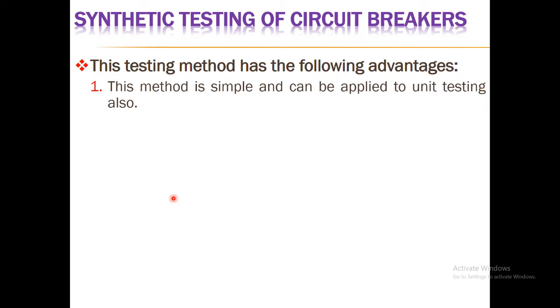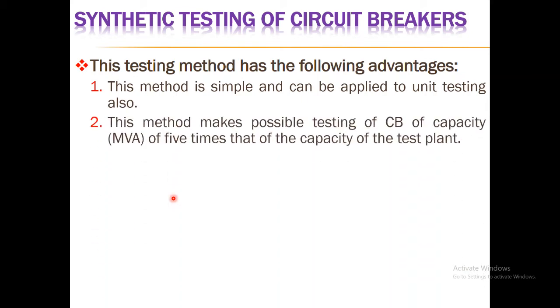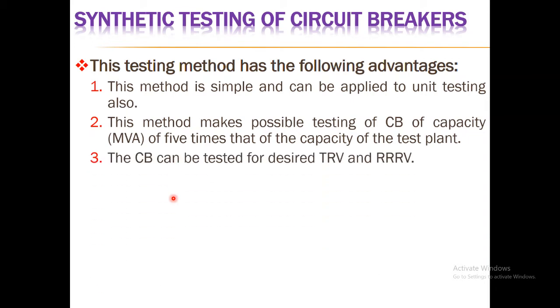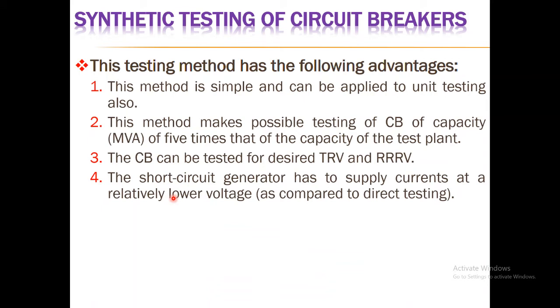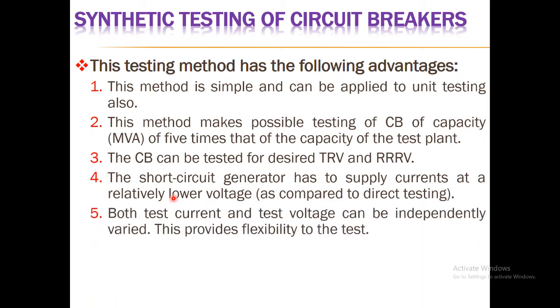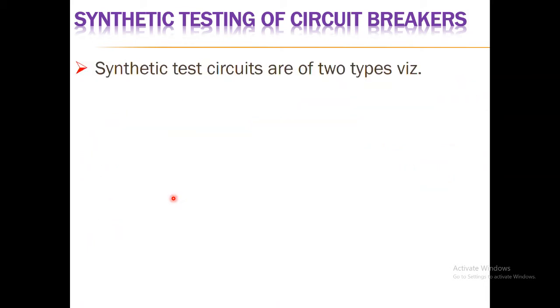The advantages of synthetic testing are: this method is very simple and can also be applied to unit testing. It makes possible to test the circuit breaker at a capacity of five times that of the short circuit generator's capacity. The circuit breaker can be tested for desired values of transient recovery voltage and rate of rise of restriking voltage. The short circuit generator supplies current at relatively lower voltage compared to direct testing, and both test current and test voltage can be independently controlled, providing better flexibility.